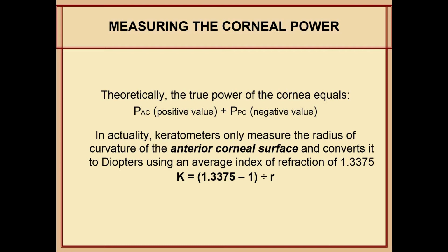However, in actuality, keratometers only measure the radius of curvature of the anterior corneal surface, and they convert it to diopters using an average index of refraction of 1.3375.